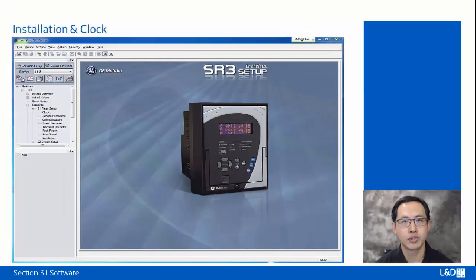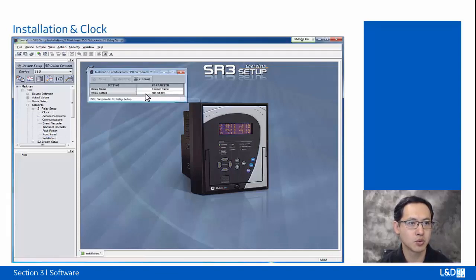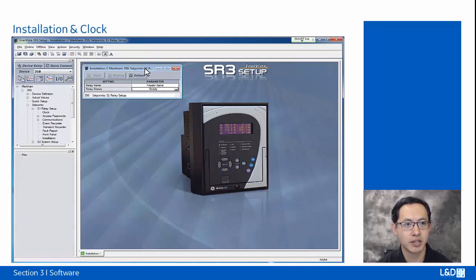When the relay is received from the factory, the relay status is not ready. So we need to set the status into ready. The setting for the status is under Set Points, S1, Relay Setup, and Installation. Double-click Installation, we can change the relay status from not ready into ready and click Save. And then we can see the front panel LED will turn on to green color for in-service.